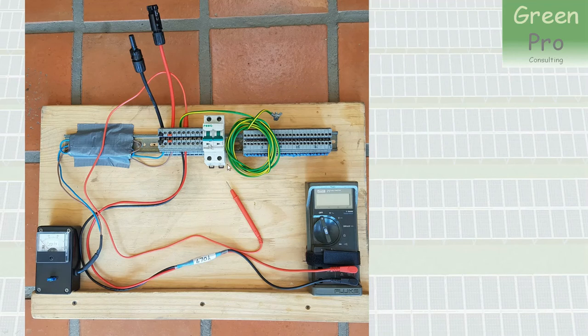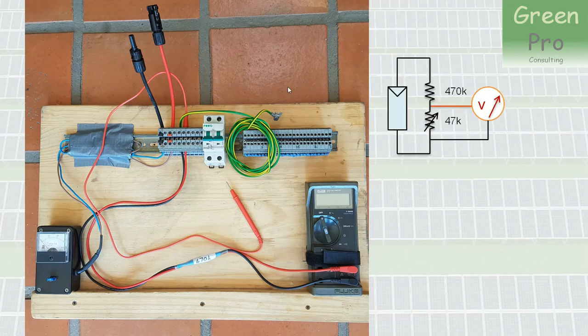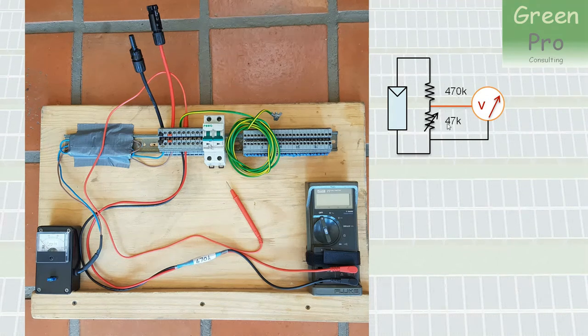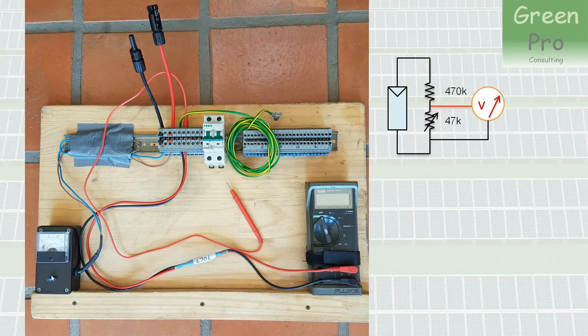Now, this meter here I actually use instead of the open and closed circuit test. What it does is when you connect the panels, it goes through a 470 kilohm 2 watt resistor, and then that forms a divider chain with a 47 kilohm adjustable resistor, which is that little one there. And you can see how I took a 30 volt meter and calibrated it in panels. So if you know you've got a 15 panel string, then you simply adjust that until you measure 15 panels there, and then you give it to the guys and they continue using that to commission the strings.